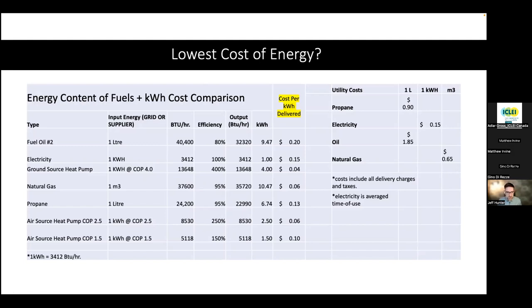How do we get that down to a common term so that we can get a real frame of reference of what is the lowest cost of energy when we're operating our systems? And we can see fuel oil number two, just for an example, we've got 40,000 BTUs per hour per liter of fuel oil. Accounting for the efficiency of the typical equipment, non-condensing, we get ourselves down to about 20 cents a kilowatt hour. Now, this is assuming oil at $1.85. We certainly saw higher than that in the last couple of years. And propane at 90 cents. So as we line all that up, we can start to see where ground source heat pumps fit as far as cost for the energy that they're delivering. And you can clearly see ground source heat pumps being the lowest cost per kilowatt hour.